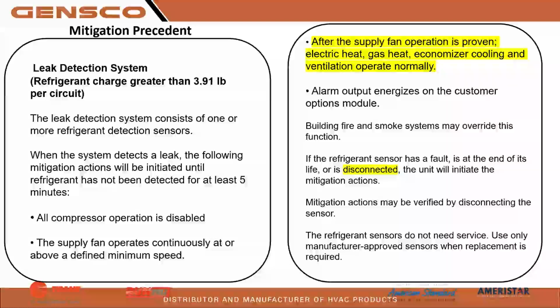So, mitigation. This is a leak detection refrigerant charge greater than 3.91 pounds. So pretty much 4 pounds. Anything above a 4-pound charge will have a leak detection system. The leak detection system consists of 1 or more refrigerant detection sensors. In the 12.5 ton and up, you're going to have 2 on the evaporator coil and only 1 on the smaller package units.